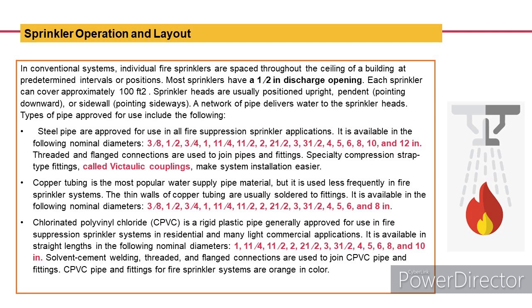The steel pipe are approved for use in all fire suppression sprinkler applications. It is available in the following nominal diameters: 3/8, 1/2, 3/4, 1, 1 1/4, 1 1/2, 2, 2 1/2, 3, 3 1/2, 4, 5, 6, 8, 10, and 12 inches. Threaded and flanged connections are used to join pipes and fittings. Specialty compression strap type fittings, called Victaulic couplings, make system installation easier.